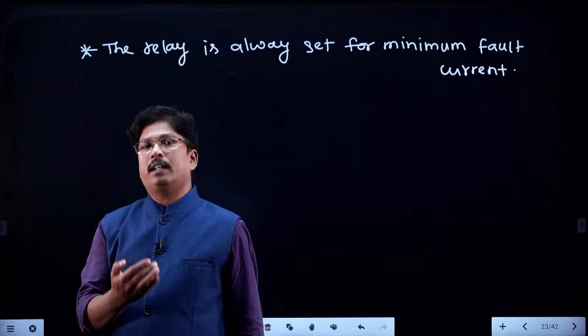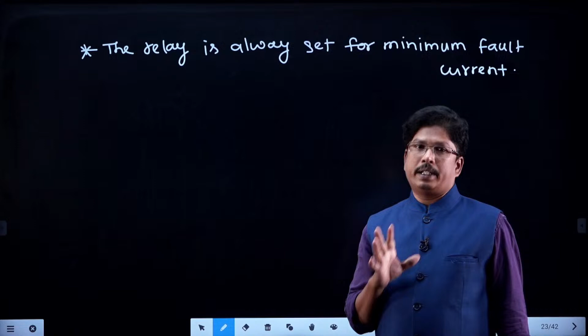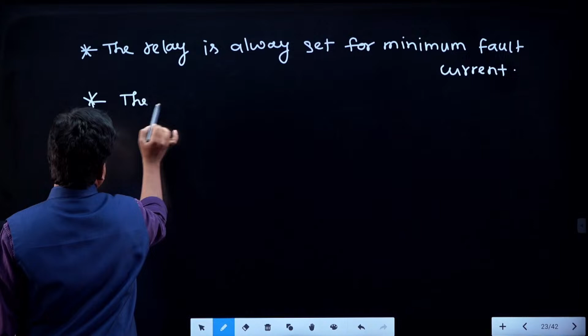Suppose the LG fault current is 10 amperes, LL is 15, LLG is 20, like that we have the currents in sequence. Suppose the relay operates for 11 amperes, automatically it can operate for 15, 20, 25, 30, and so on. That is why we always set the relay for the minimum fault current. And the circuit breaker is always set for maximum fault current.